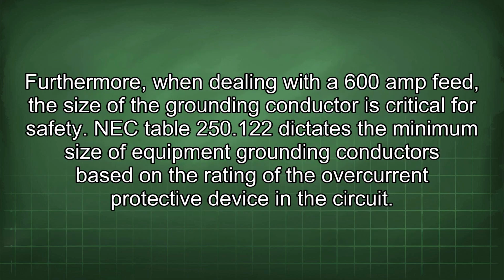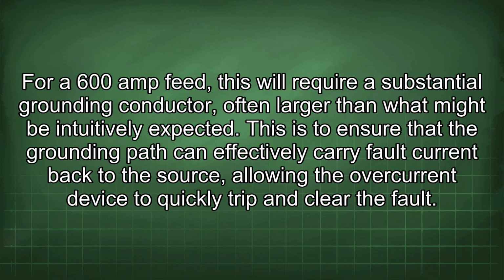Furthermore, when dealing with a 600 amp feed, the size of the grounding conductor is critical for safety. NEC Table 250.122 dictates the minimum size of equipment grounding conductors based on the rating of the overcurrent protective device in the circuit. For a 600 amp feed, this will require a substantial grounding conductor, often larger than what might be intuitively expected. This is to ensure that the grounding path can effectively carry fault current back to the source, allowing the overcurrent device to quickly trip and clear the fault.